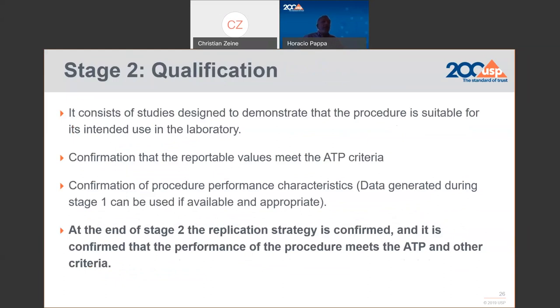Stage 2 is the qualification of the method—this is where we actually perform the validation. It is mostly focused on accuracy and precision. If we can demonstrate that the accuracy and precision of the method are adequate within the range of the method and meet the ATP requirements, we can say the method is qualified. We also have data generated during Stage 1 that include the rest of the performance characteristics such as linearity and limit of quantitation. At the end of Stage 2, the replication strategy is confirmed and it is confirmed that the procedure performance meets the ATP and other criteria. The method is then ready to implement.